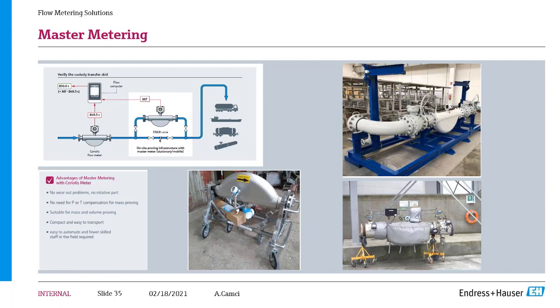Master metering with a Coriolis meter has the same advantages as the meter itself: no wear and tear, no rotating parts, and no pressure and temperature compensation for mass proving. It is also suitable for volume proving. It is compact and easy to transport. You see some examples: some trolley examples, some heating jacket installations, or it can even be mounted on a frame on a skid. But if you have different locations, what happens?